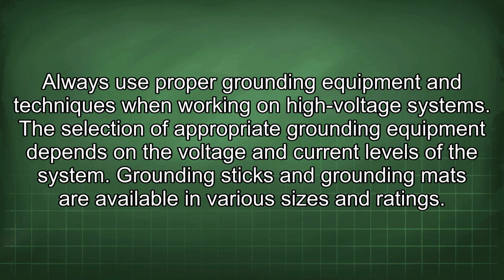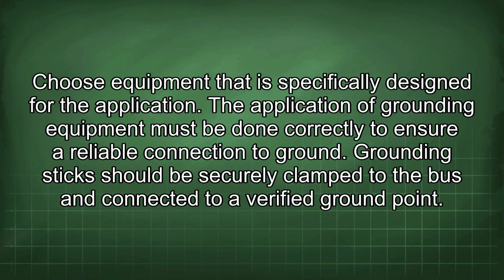Always use proper grounding equipment and techniques when working on high-voltage systems. The selection of appropriate grounding equipment depends on the voltage and current levels of the system. Grounding sticks and grounding mats are available in various sizes and ratings. Choose equipment that is specifically designed for the application. The application of grounding equipment must be done correctly to ensure a reliable connection to ground.